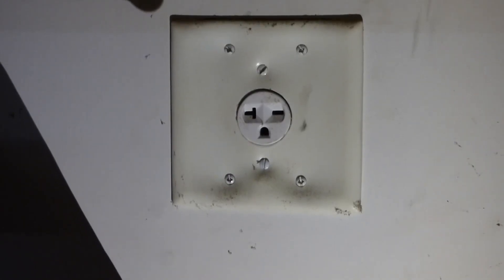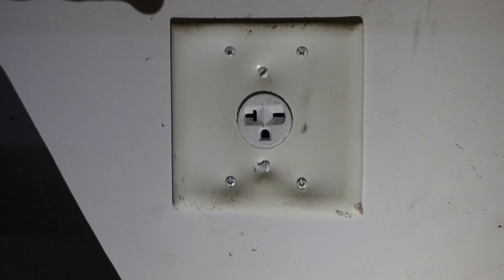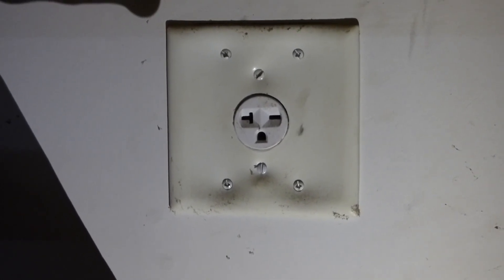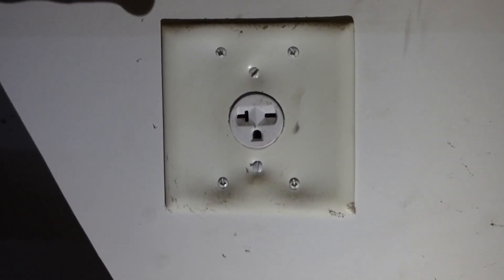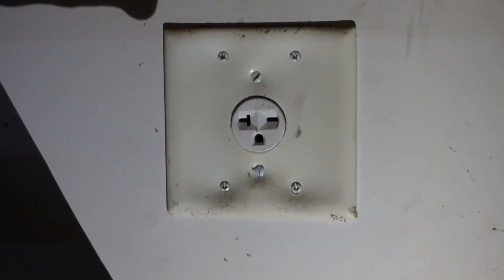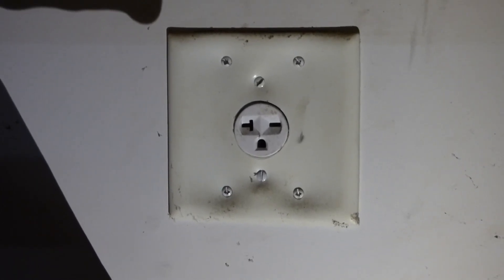Here's an outlet that overheated. You can see the plastic plate has melted, and it's actually a little bit of a brown color. Make sure your wire connections are tight.